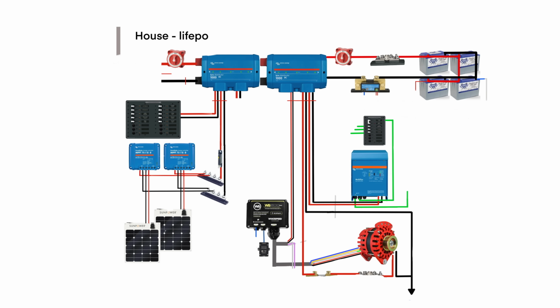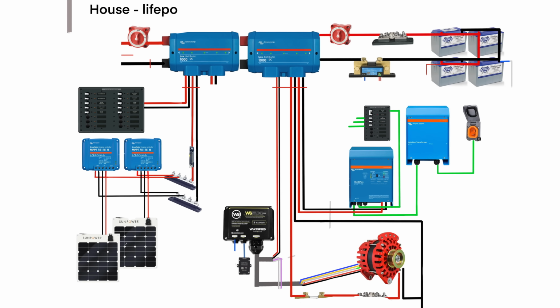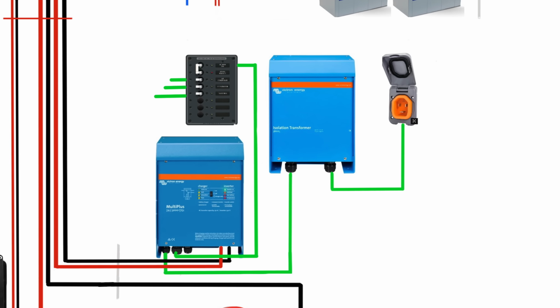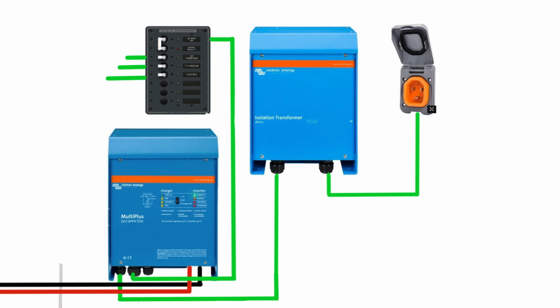Along with that, we are also installing an isolation transformer, but we haven't gotten to it yet because it hasn't arrived. An isolation transformer is used to transfer AC power from the source to the loads without an actual mechanical connection—the loads are transferred magnetically. It has two coils: picture one coil energized, and magnetically it's transferred to the other coil. So there's no physical connection, which gives you isolation.